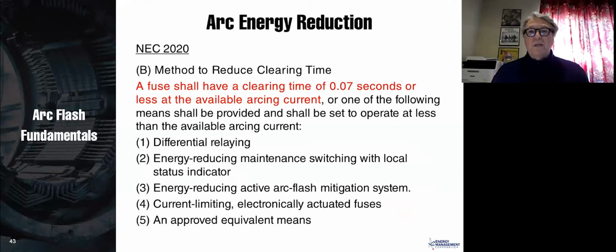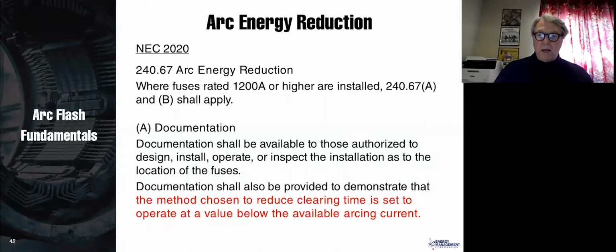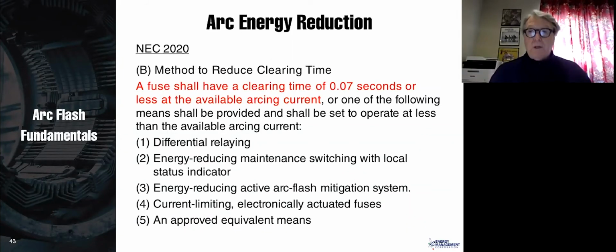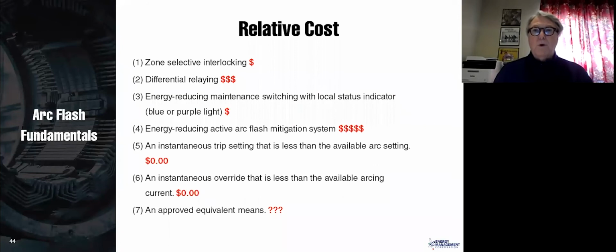NEC 2020, this is part B. And again, we're talking about fuses. This was part A. Now we get to part B. A fuse shall have a clearing time of 0.07 seconds or less at the available arcing current. We're not talking about fault current. We're talking about arcing current. How do you know what the arcing current is? Well, you don't unless you do an arc flash study. And then they have mentioned some other things that you can do with fuses if you don't have that 0.07 seconds. So there are lots of fuse requirements there.